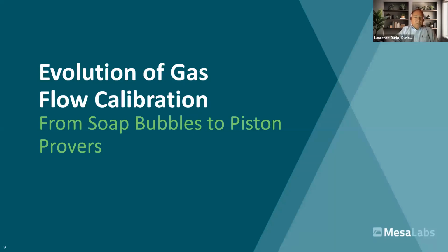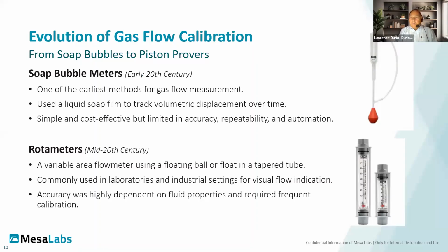Started out back when I was young, we had dinosaurs. We used soap bubble meters. They work reasonably well. Run a soap bubble up a burette of a known volume, at least we hoped it was known. I checked some of the early commercial ones and they were off by sometimes as much as 7, 8, 10%. We would time it with a hand-operated stopwatch. It was simple, it was cost-effective, it was probably the best available at the time from a field perspective, but we had accuracy limitations based on some of the commercially available burettes.